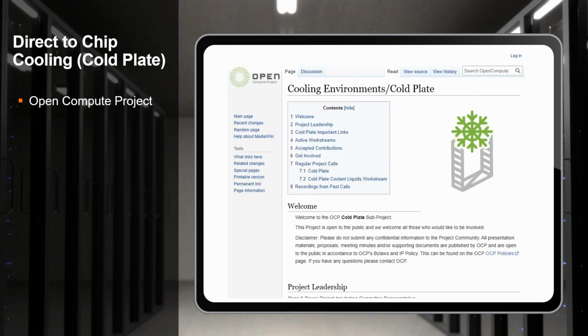We always like to point you to the Open Compute project if you want detailed information and reference designs about cold plate applications. These guys are the experts. If you're not familiar with OCP, it's a third-party think tank type organization, and they do an excellent job of creating white paper documentation and reference designs for things that are new or interesting in the industry. They have a working group that's specifically working on cold plates. They have other ones that are specifically working on how to connect cold plates to the rest of your system, how to design a cooling loop inside a technology space, how to do a CDU. They got groups for everything.